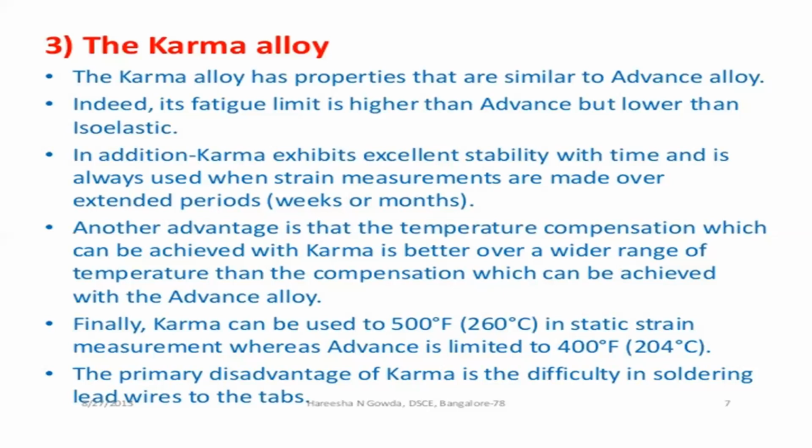Another advantage is that the temperature compensation which can be achieved with Karma is better over a wider range of temperature than the compensation which can be achieved with the Advance alloy. So the temperature compensation is very high in this Karma alloy. So it will be used over a wider range of temperatures in these strain gauges.